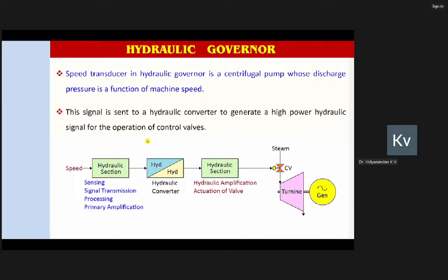What you are seeing is basically the KWU turbine Siemens concept. So they sense the speed hydraulically, process it hydraulically, transmit it hydraulically, and amplify it hydraulically. Why? Because control valves were hydraulically operated. Even today, the best of steam turbine control valves are hydraulically operated. Of course, in Germany, I understand that they have some electrically operated control valves on turbines because of the high temperature, maybe 600 degrees, 625 degrees Celsius, and the current Alstom unit. So motors will not withstand that temperature, so they are hydraulic. Accordingly, you need a hydraulic pressure signal for the operation of the control valves.